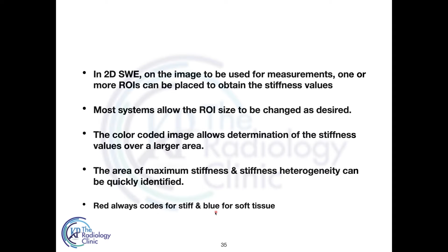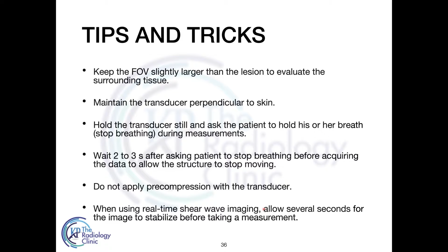Here, the red always codes for the stiff and the blue for soft, whereas in strain, the blue was for hard and red was for soft. Some tips and tricks: keep the FOV slightly larger than the lesion to evaluate the surrounding tissue. Maintain the transducer perpendicular to the skin. Hold the transducer still and ask the patient to hold his or her breath during the measurements. Wait 2 to 3 seconds after asking the patient to stop breathing before acquiring the data to allow for the structure to stop moving. Do not apply pre-compression with the transducer. When using real-time shear wave imaging, allow several seconds for the image to stabilize before taking a measurement.